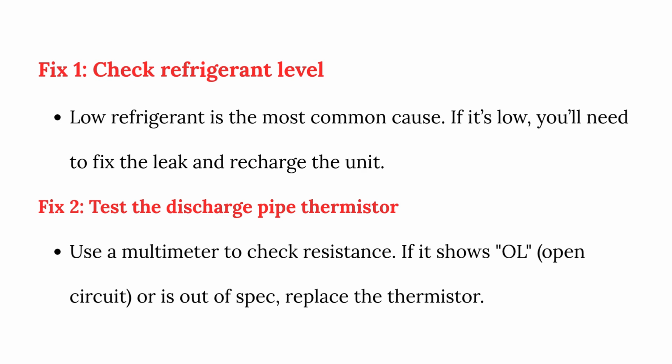Fix 1. Check refrigerant level. Low refrigerant is the most common cause. If it's low, you'll need to fix the leak and recharge the unit.